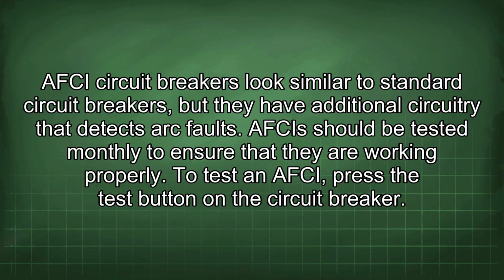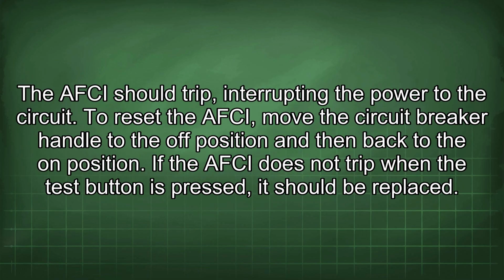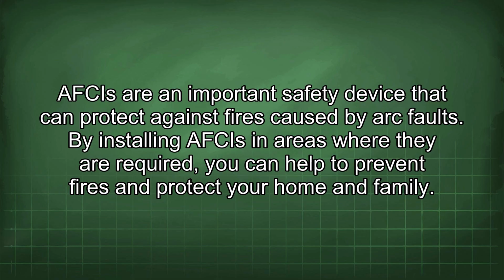AFCIs should be tested monthly to ensure that they are working properly. To test an AFCI, press the test button on the circuit breaker. The AFCI should trip, interrupting the power to the circuit. To reset the AFCI, move the circuit breaker handle to the off position and then back to the on position. If the AFCI does not trip when the test button is pressed, it should be replaced. AFCIs are an important safety device that can protect against fires caused by arc faults. By installing AFCIs in areas where they are required, you can help to prevent fires and protect your home and family.